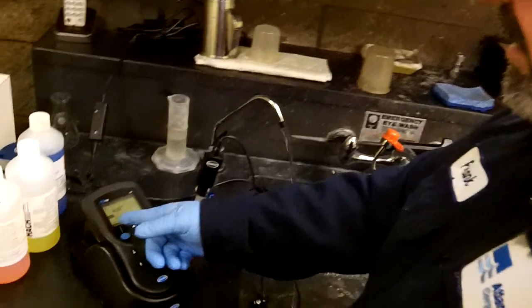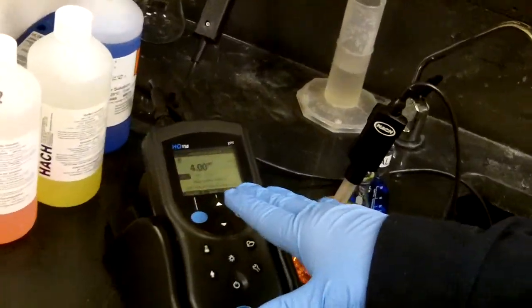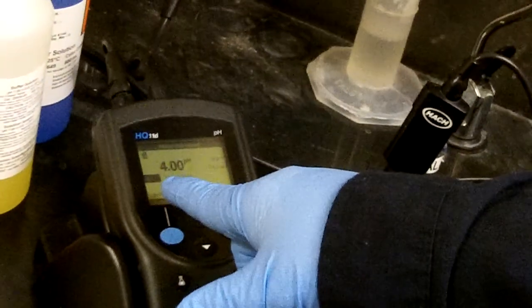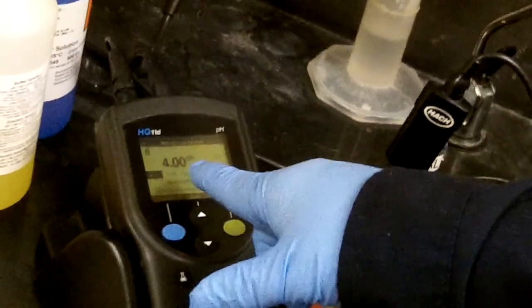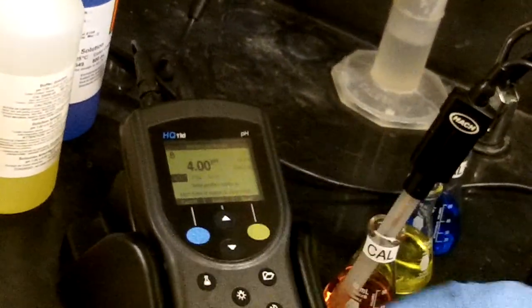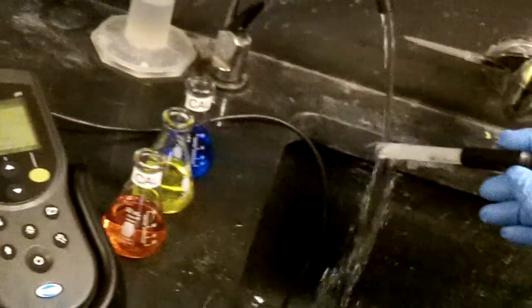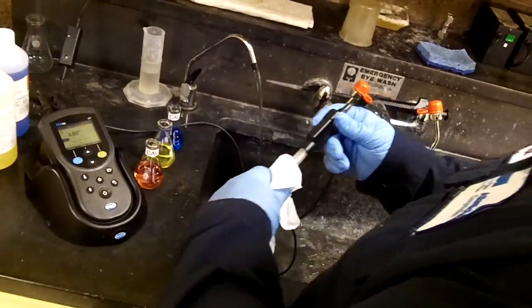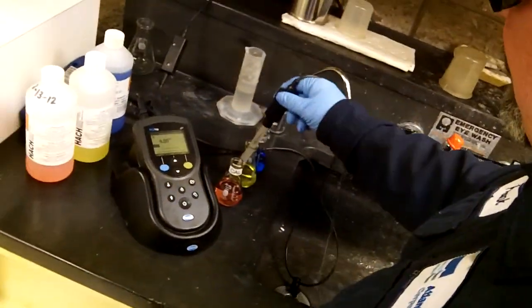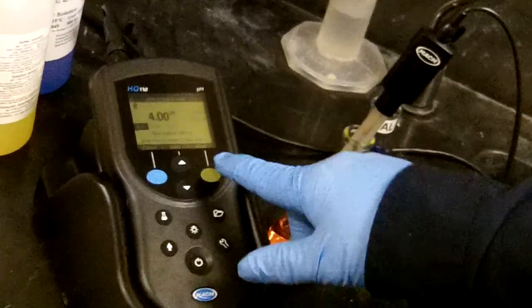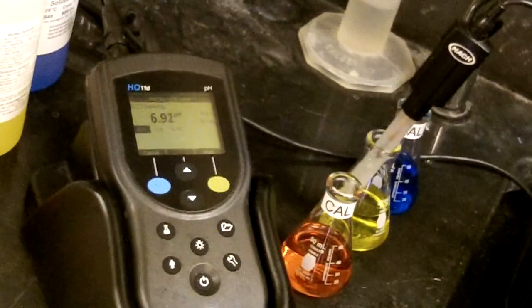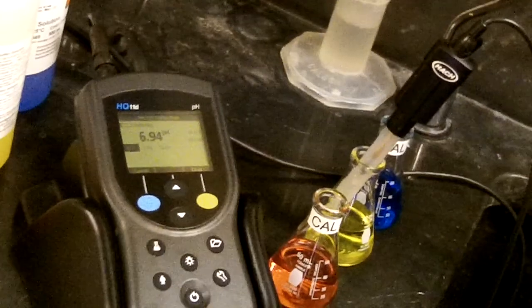So here this came out at 4. You know that it's done doing what it's going to do when it's blocked off in black over the number that you're trying to calibrate to. So 4 is done. We're going to take it out of the 4 cal. We're going to rinse it with DI water. We're going to wipe it dry. We're going to put it in the 7 buffer and hit read, and then the 7 buffer is going to start.